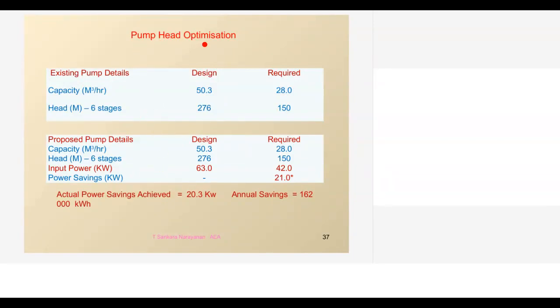So they are having two pumps, 100% standby is there. One pump has a reduced number of stages. Another pump is having full capacity. So whenever the system requires the maximum requirement, I can run the standby unit, which is as per the original design. So these type of measurements we have to do and go closer to see where all the opportunities are. Otherwise, per se, electricity saving is not so easy in a plant.